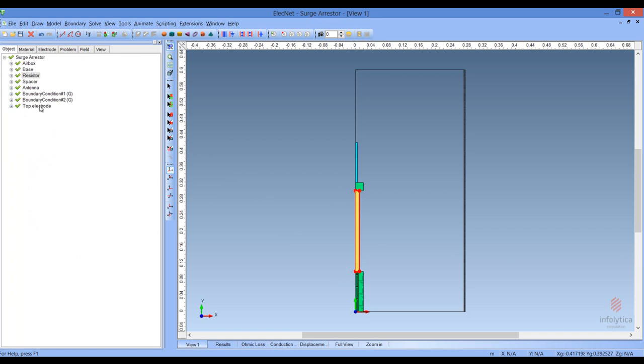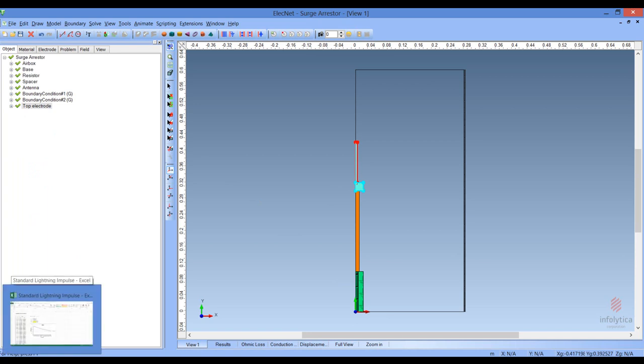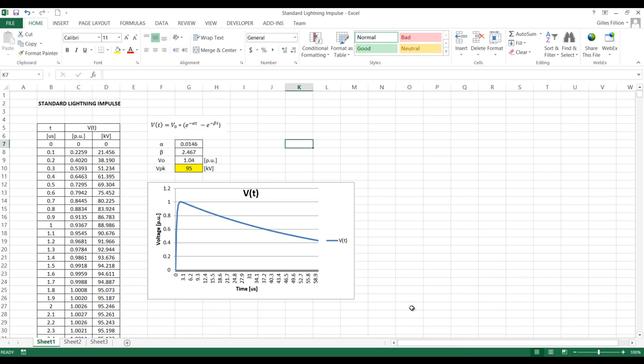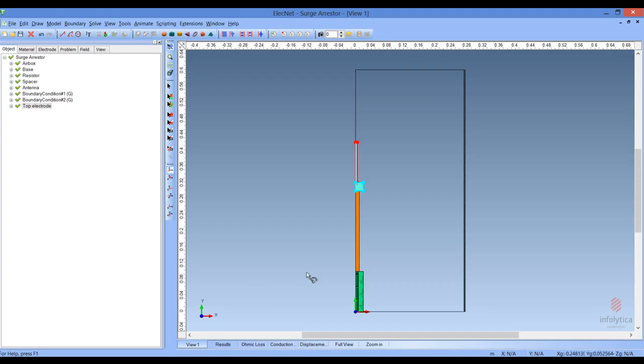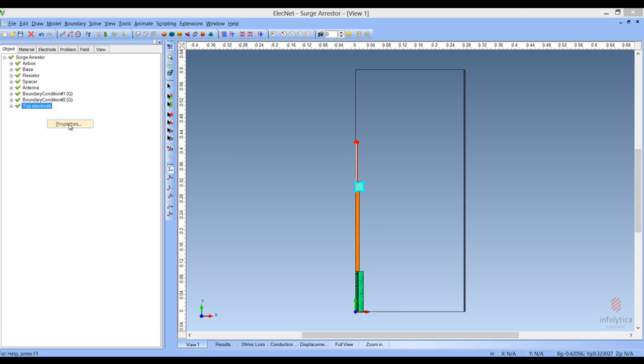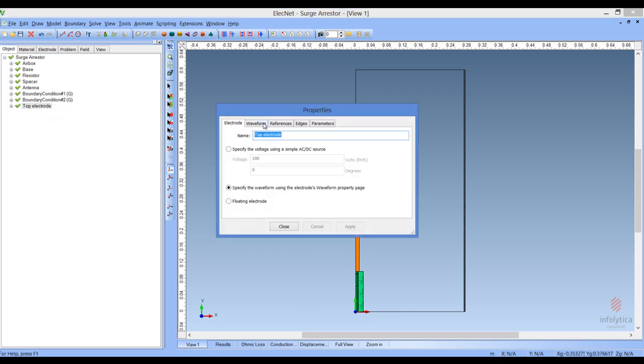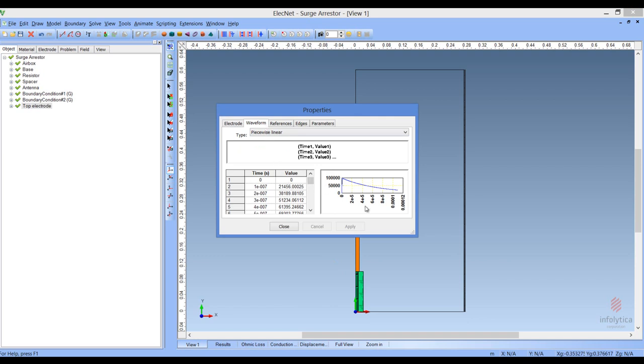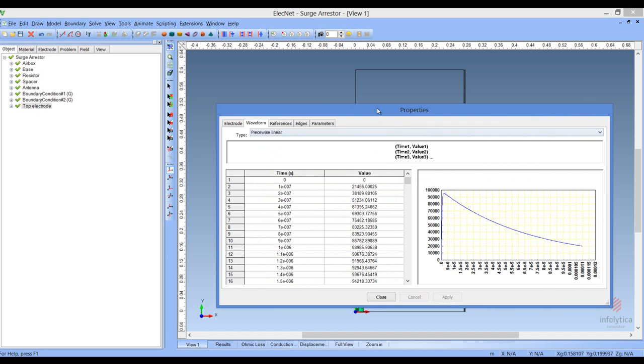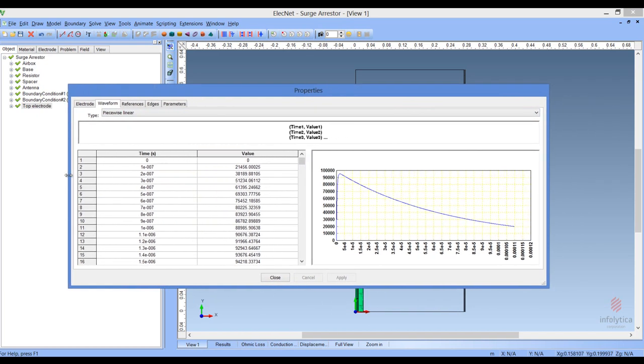This could just as well have been a nonlinear material with potential, and that would have worked just as well. Going back now to the electrode, let's have a look at how we define it. First, I would like to show you what the voltage should look like. Here we have a model of a standard lightning pulse — the equation for the voltage — and this is the waveform we'll enter. I've taken that data and put it into the model. The electrode properties are specified using a waveform, and as you can see it matches what we had entered from the spreadsheet.